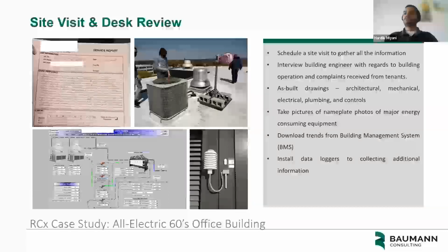Having as-built drawings of the building is really important, as it provides details of the building characteristics in terms of the building envelope, like how it was constructed initially in the 1960s. What were the initial mechanical, electrical systems that it was designed for? What was the ventilation schedule? What were the initial lighting counts? There are very high chances that the floor plan and the systems change or get upgraded over a period of time. Hence, it is very necessary for us to take nameplate pictures of all the major energy consuming equipment on site. So that was something that we did for this particular project.